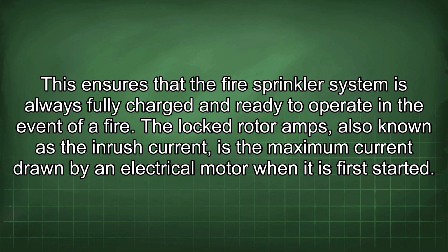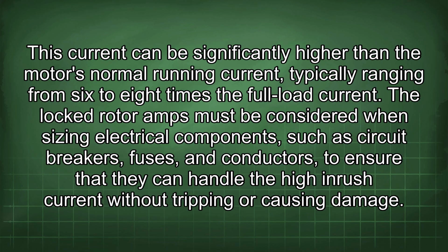The locked rotor amps, also known as the inrush current, is the maximum current drawn by an electrical motor when it is first started. This current can be significantly higher than the motor's normal running current, typically ranging from 6 to 8 times the full load current. The locked rotor amps must be considered when sizing electrical components such as circuit breakers, fuses, and conductors to ensure that they can handle the high inrush current without tripping or causing damage.